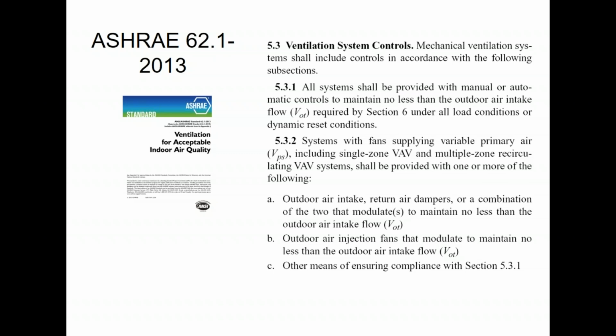So the normal way to do that would be to have two dampers, outside air and return air, modulating to maintain the outside air intake. The reason they reference it this way in relation to the supply fans and the staging is because if I put in a 2-speed fan and I slow it down to the lower speed, it's going to inadvertently reduce my outside air intake CFM. So if I have a 2-speed fan, I then have 2 minimum positions for ventilation that I have to maintain. One if my fan is on 100%, the other if my fan is on 67%. So a traditional economizer controller would not be able to do that. You would need DDC controls, or if you had a simple thermostat system, you would need a JADE-type economizer controller with dual minimum ventilation positions.